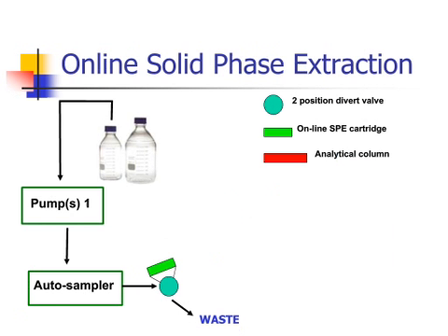Unfortunately, just doing a straight protein precipitation leaves you with a fairly dirty sample, and that dirty sample contains an awful lot of phospholipids. So we have to clean the sample up online on the instrument, and we do that by using online solid phase extraction. So we have one set of pumps on the HPLC which pump your sample through the autosampler to a switching valve where it goes onto an online solid phase extraction cartridge.